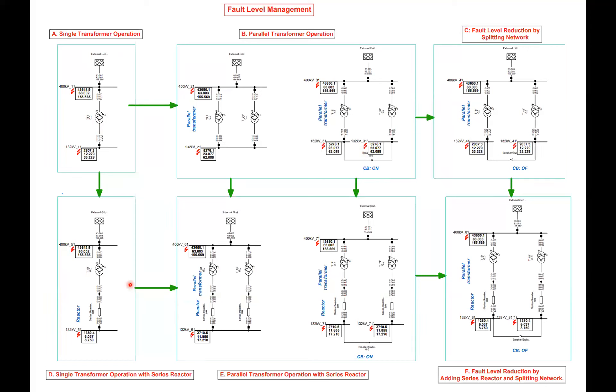Another scenario is adding a reactor in series with the transformer. As soon as we add a reactor with the transformer, the impedance will be high and the current will reduce. For example, comparing with the 12 kiloamp case, it is now reduced to 6 kiloamps because of the impedance of the reactor. Then, looking at the parallel transformer with added series reactors, the fault current reduces from 23 kiloamps down to 11 kiloamps — almost half.